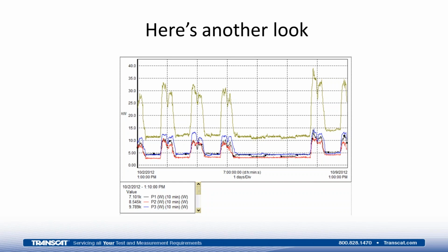If I'm not using a device that is true RMS, it is not capable of picking up those fluctuations and will therefore misrepresent the value. So in power and power quality systems, it's important and critical that the device you're using is a true RMS measuring device to give you the real values and not a misrepresentation of those values. Thank you, Nicole. Thanks. One more, unless we get another one that comes in.